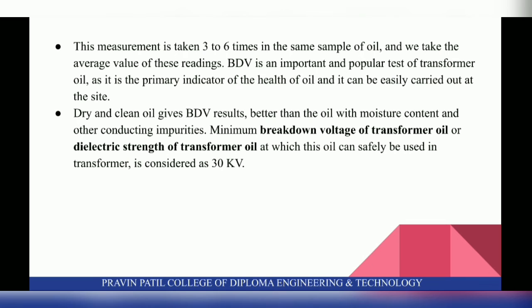This measurement is taken 3 to 6 times on the same sample of oil, and we take the average value of these readings. BDV is an important and popular test of transformer oil as it is the primary indicator of the health of oil, and it can be easily carried out at the site.